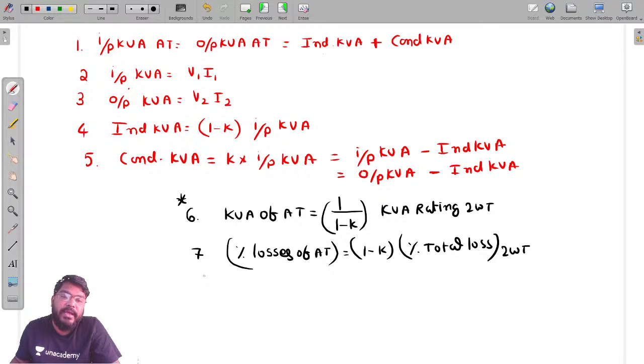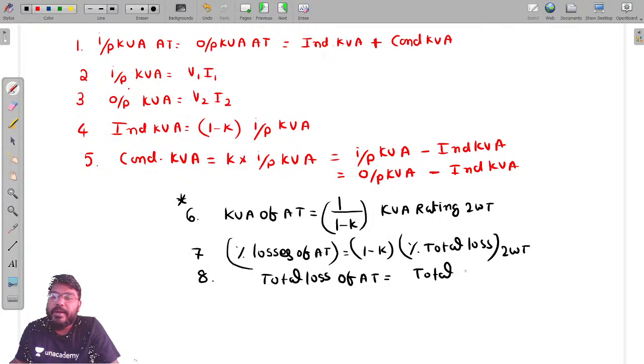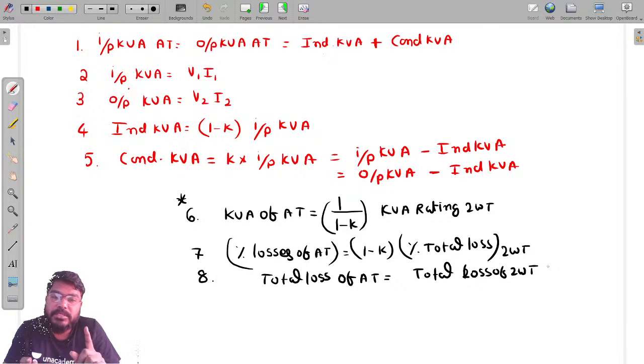There is another formula: total loss of auto transformer is equal to the total loss of the two winding transformer. These are very important formulas. Percentage losses are 1 minus K times of the percentage total losses of the two winding transformer, but total loss of auto transformer is equal to the total loss of the two winding transformer.